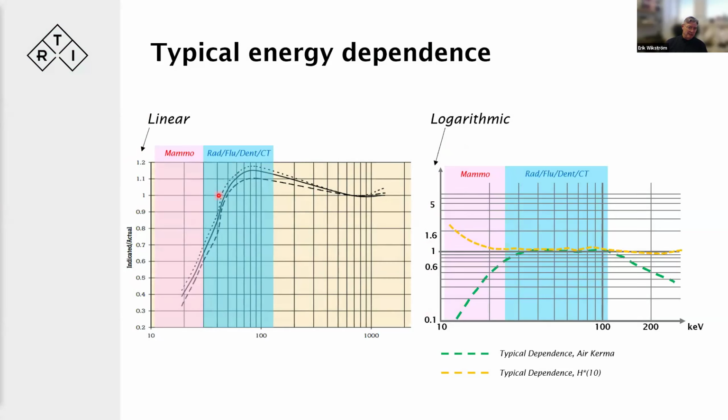So here you see that this is one where the reading is proper, and it happens only up here, which is around 800 keV, and down here, which is 20, 30, 40, 50 keV. That's when it shows the right value. For other values, we need to compensate. And then we need to know the energy range, and pretty precisely, because this is a very steep curve.